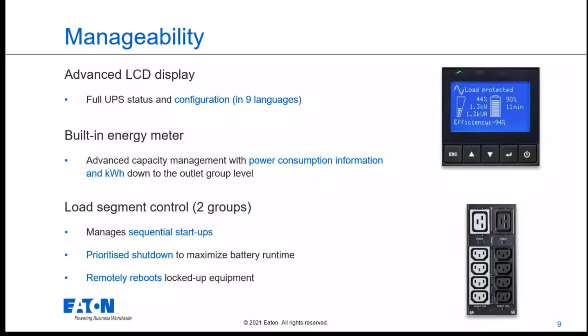You also have the ability to prioritize the shutdown to maximize the battery backup. For instance, you can have non-critical equipment plugged to group 1 and others to group 2. After 10 minutes you stop group 1, and after 15 minutes you stop group 2. So you are able to reduce the load on the UPS and increase the runtime for the critical loads. And of course you can do on and off and remotely reboot the locked equipment plugged on group 1 and group 2.